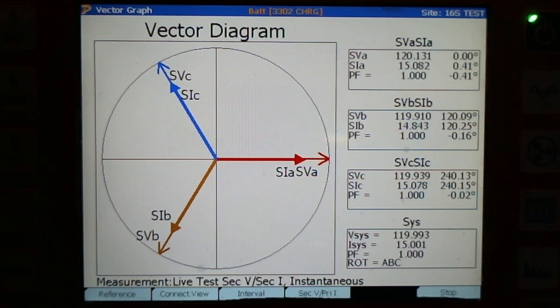Again, if you're not sure how much current you're dealing with in the meter can, pull out your clamp-on meter and measure current. But anyway, we've got 120 volts on all three phases, and as Chris mentioned earlier, we've got 15 amps and 120 degrees apart.